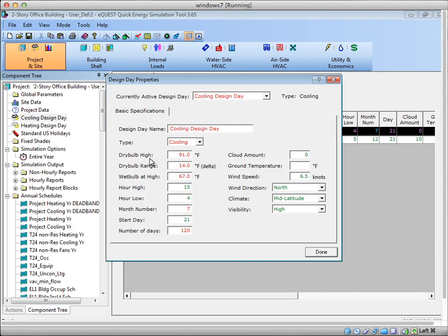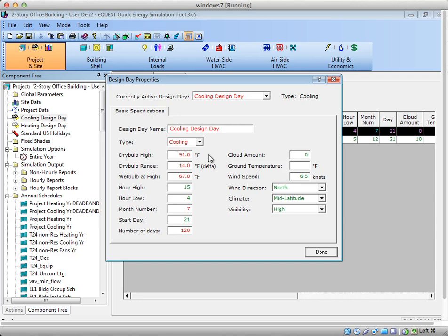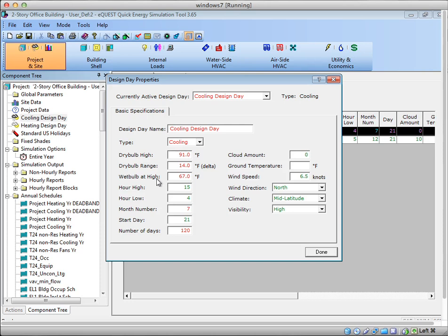So it asks for the highest dry bulb and the reason you might specify this is because you may want to size equipment at a hotter temperature than the weather file peaks at. For a lot of locations, a weather file, which is a typical average year, will have a high that maybe isn't an extreme or maybe isn't a 0.4 or 1% condition, such as ASHRAE might define. So for eQuest, this is where you can create your design day, so you have to put in the high dry bulb you would like equipment to be sized at. The dry bulb range specifies what the difference is between the hottest temperature and the lowest temperature on this design day.